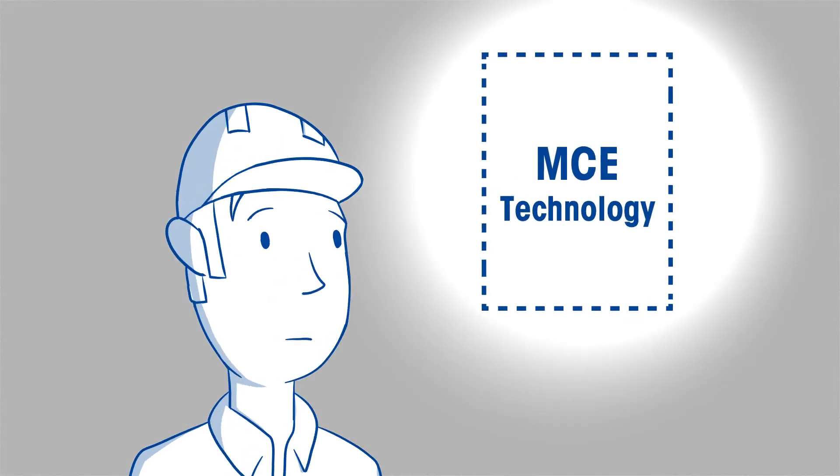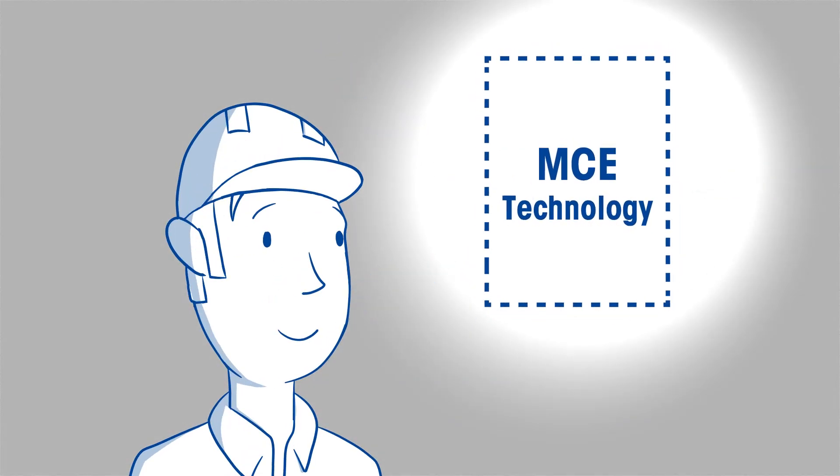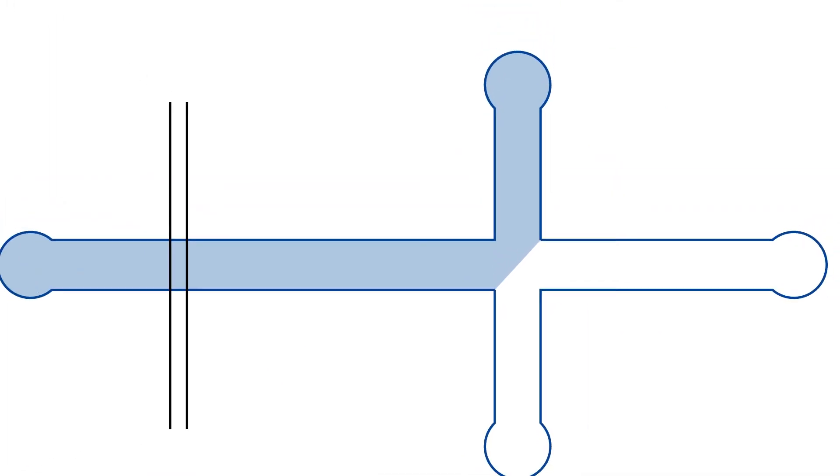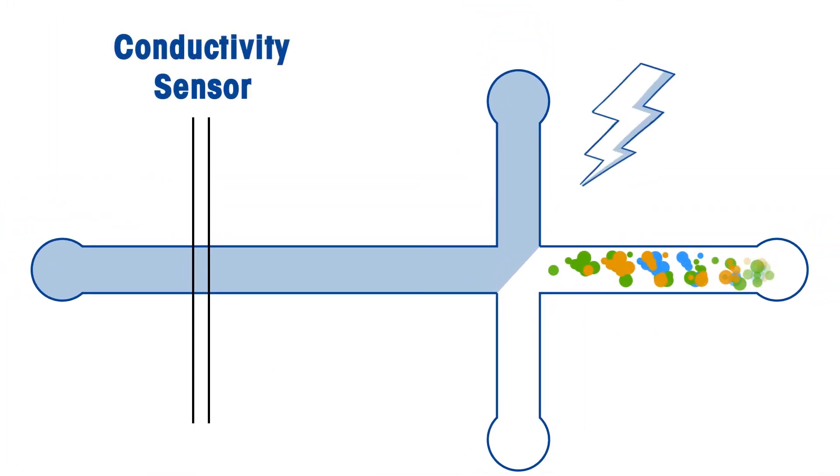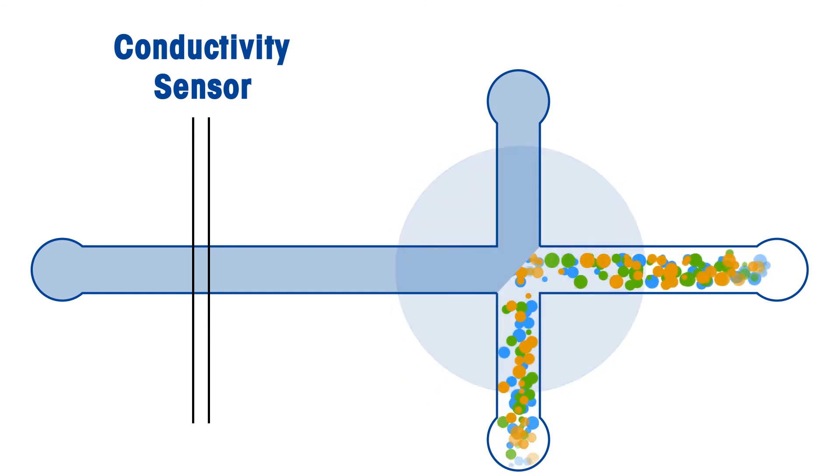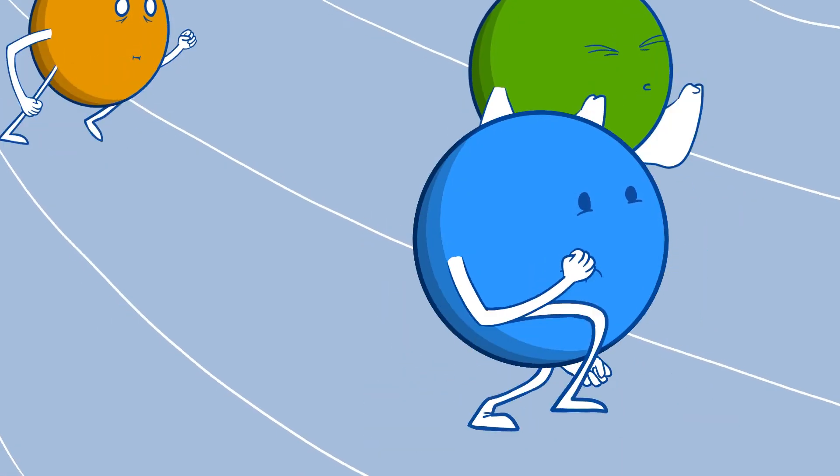Microfluidic capillary electrophoresis, MCE, fills this need. MCE uses an electric field to separate ions in a capillary on a cartridge based on their mobilities. Different ions move through the capillary at different speeds, and they eventually pass a conductivity sensor near the end of the capillary where the response is based on their concentration.